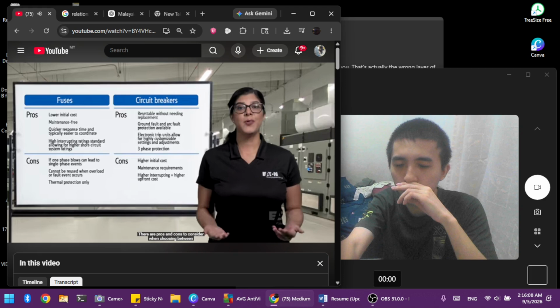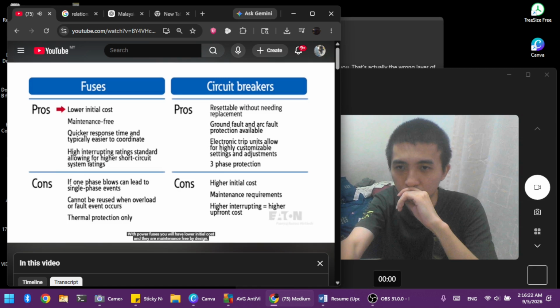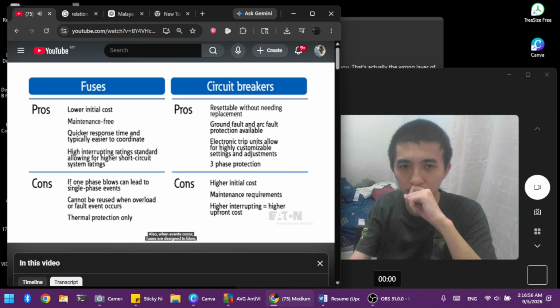With power fuses, you will have lower initial costs and they are maintenance free by design. You will also have a quicker response time and higher interrupting ratings as a standard, which allows for easy coordination and higher fault protection of downstream equipment. However, power fuses only provide single-phase protection, so if a fault occurs, it can lead to single-phase events. And motors that see single-phasing can overheat and may be damaged over time. Also, when events occur, fuses are designed to blow, which means they must be replaced, leading to potential costs.